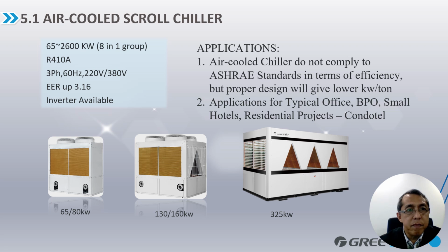For the application of the air-cooled scroll chiller, actually air-cooled chillers do not comply with the ASHRAE standard in terms of efficiency if you look at the nameplate. But if you design it properly, it will give you a lower kilowatt per ton system efficiency. Application is it can be used for typical office, BPO, small hotels, residential projects, or condo hotels.